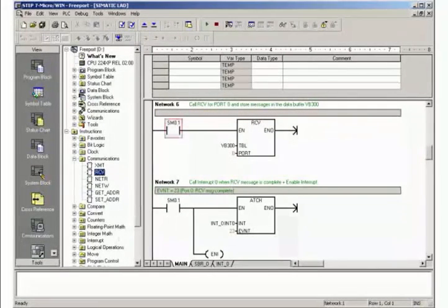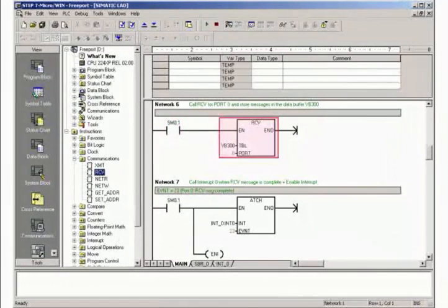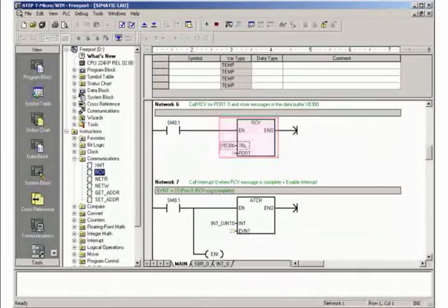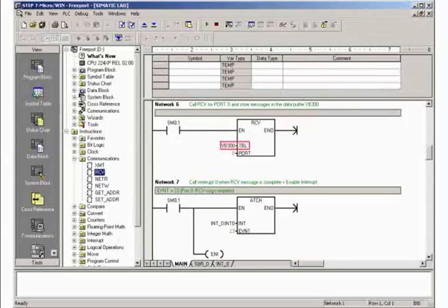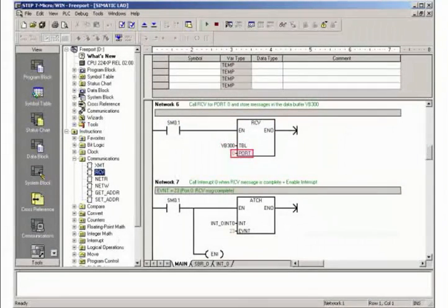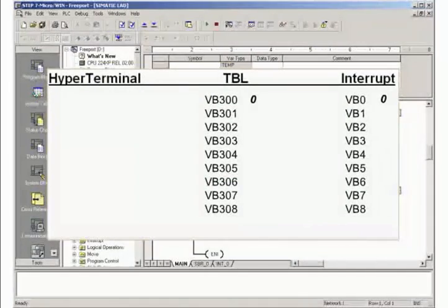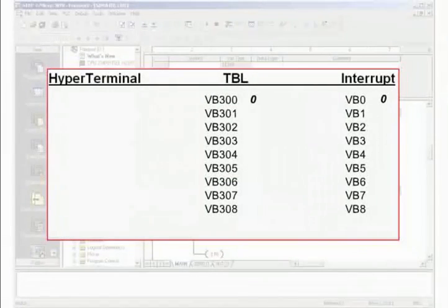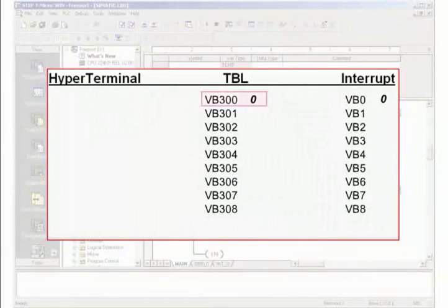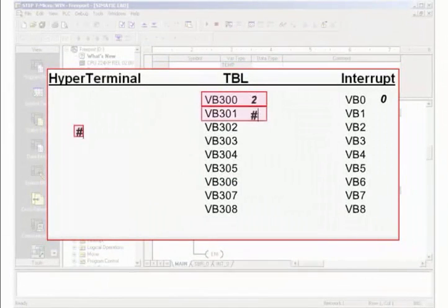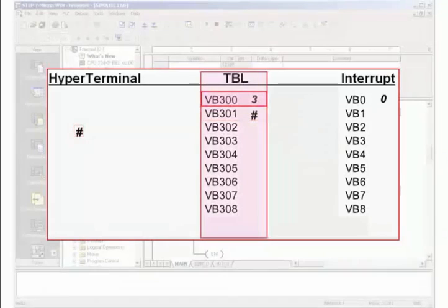In Network 6 you initialize the calling of receive block RCV. Specify the start address for the data buffer and select port 0. With the RCV function every character is counted upon detection of the start character and written into the data buffer TBL.